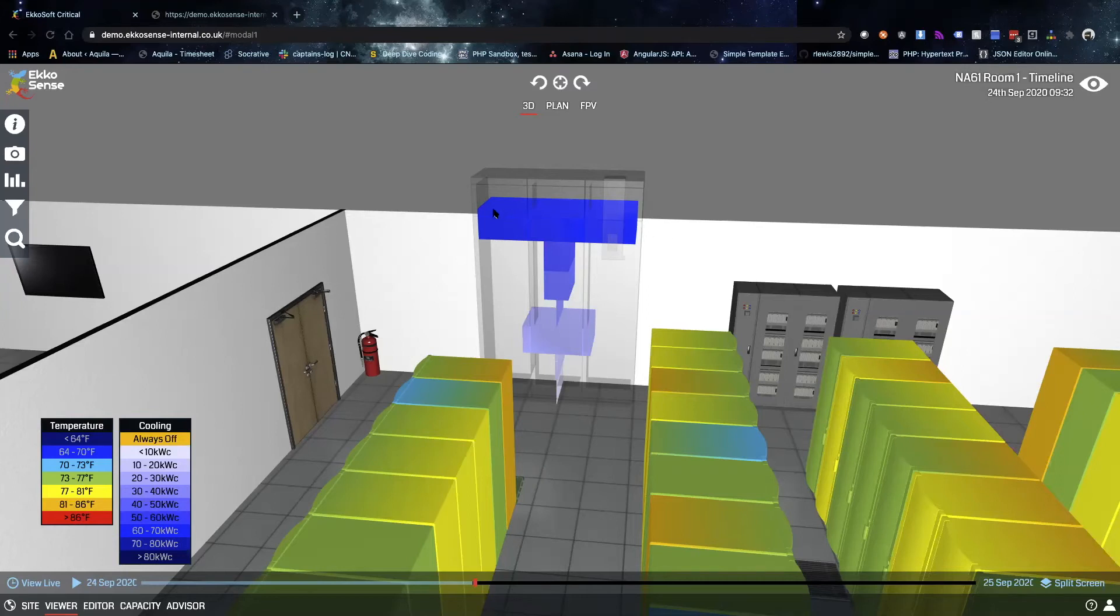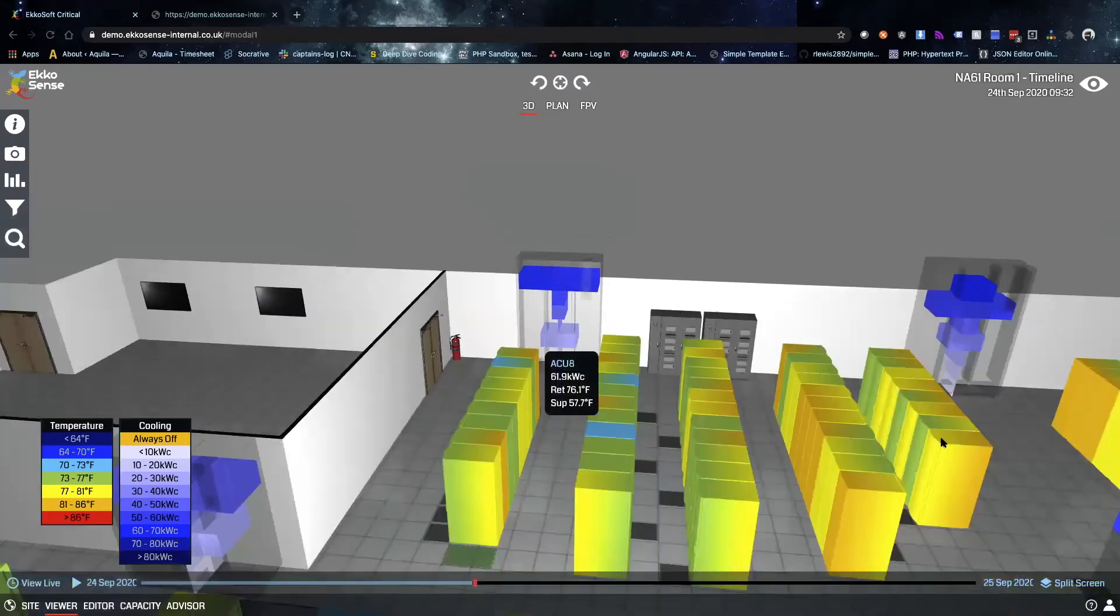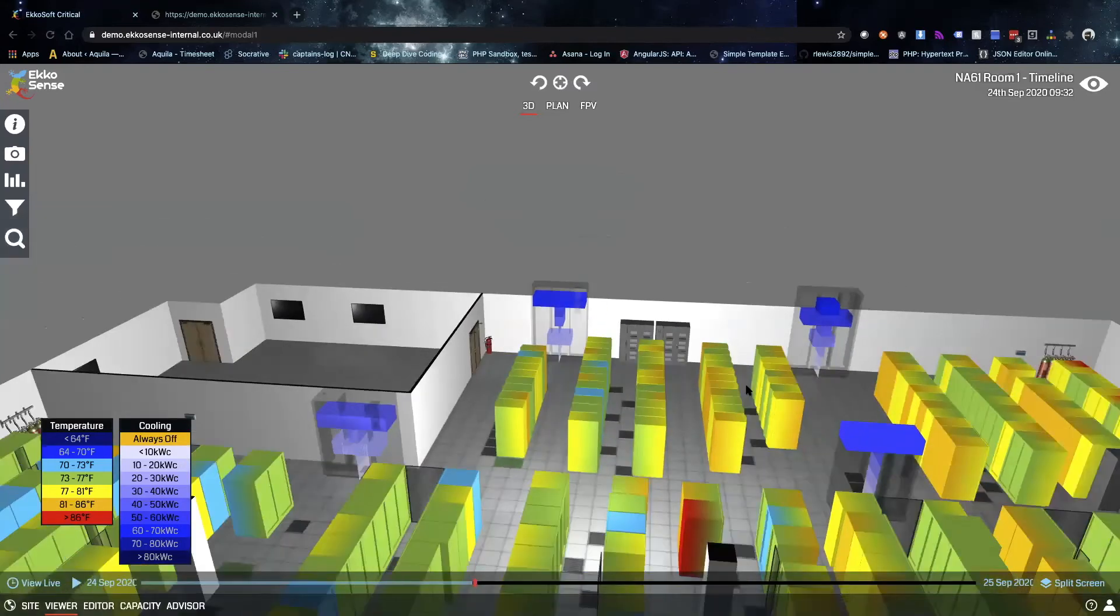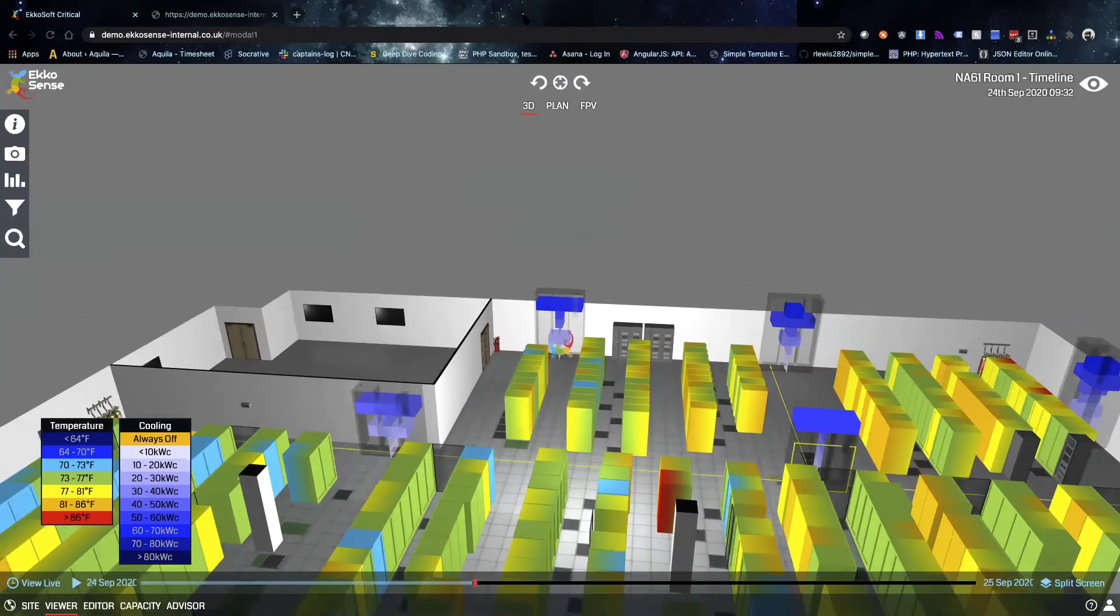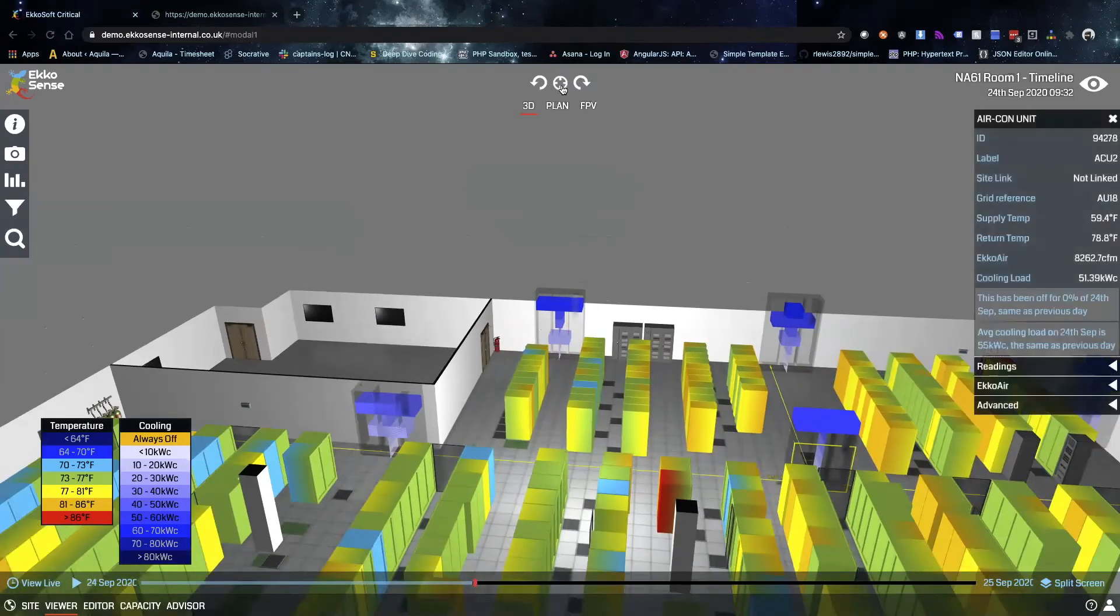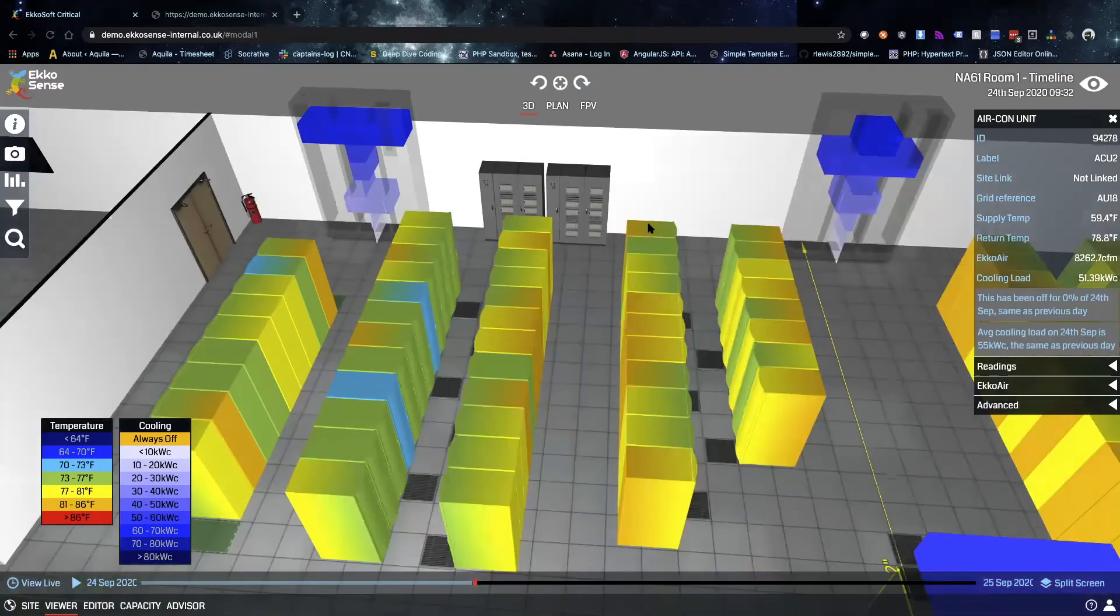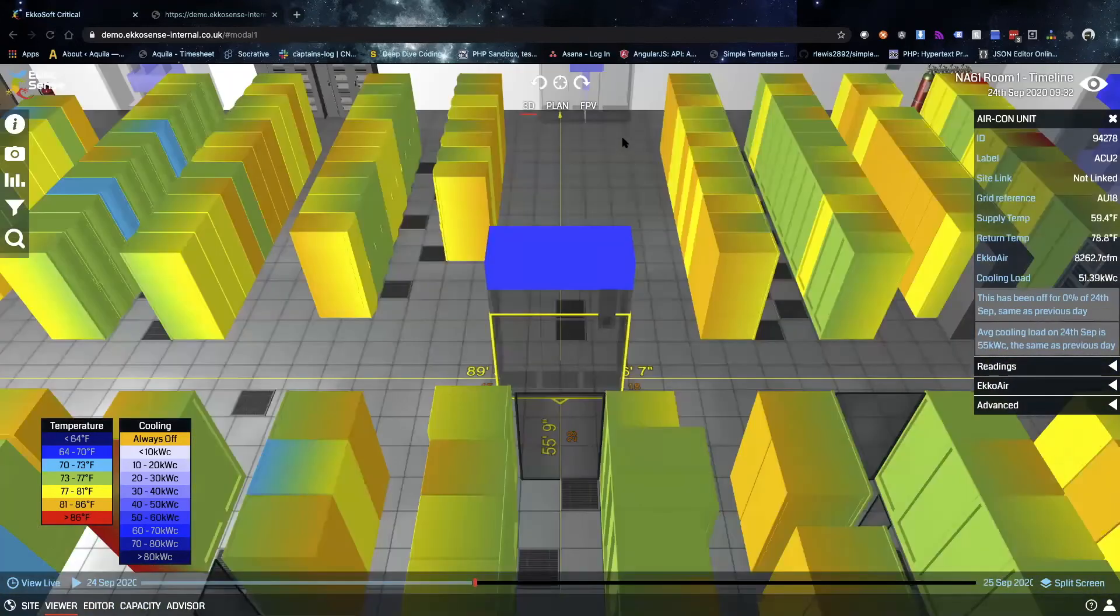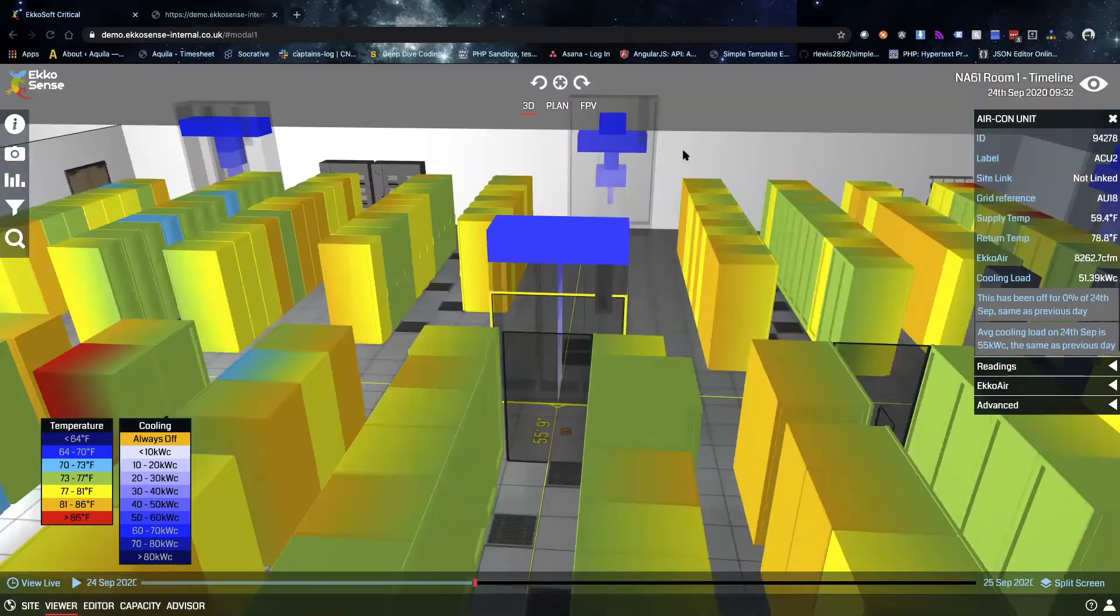You see the widest bar happens to be on the top in that dark blue, and so that's showing that most of the time in the last 24 hours this cooling unit has been delivering between 60 and 70 kilowatts of cooling capacity. Down towards the bottom there's another bar that's substantial, maybe about 25% of the time the cooling unit has been delivering somewhere between 20 and 30 kilowatts of cooling.